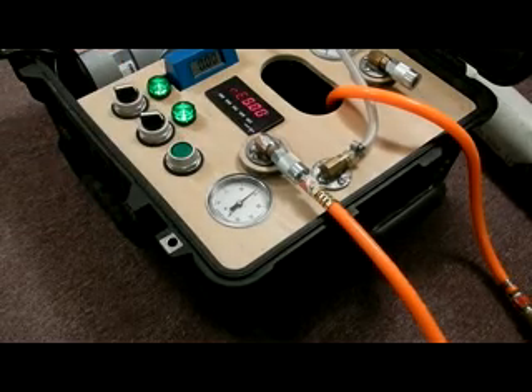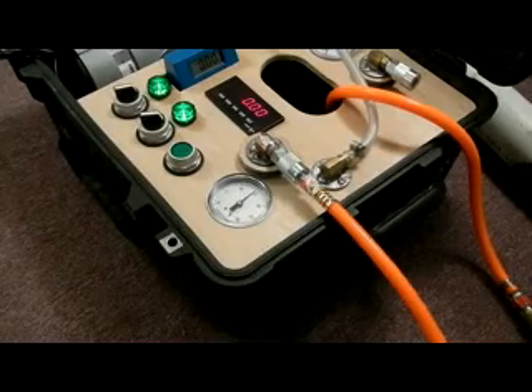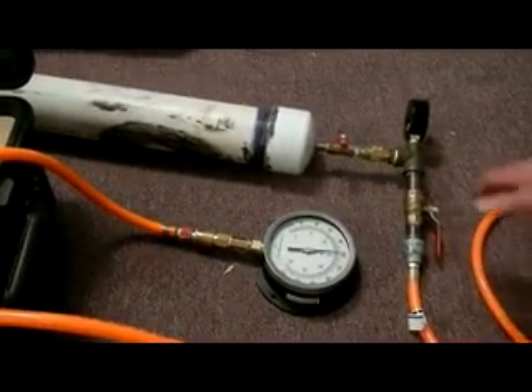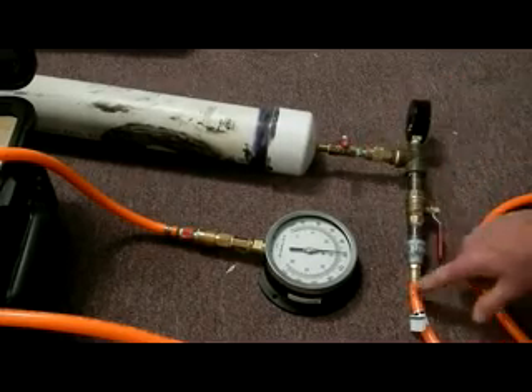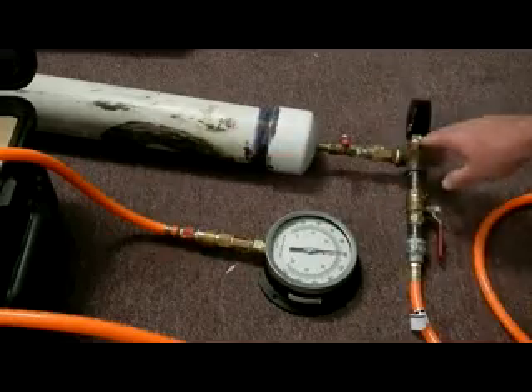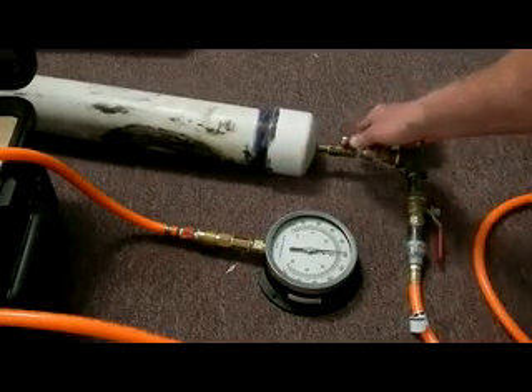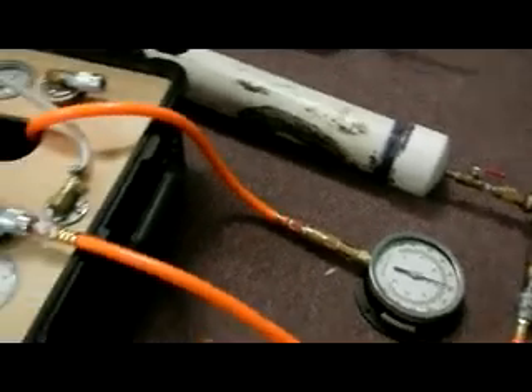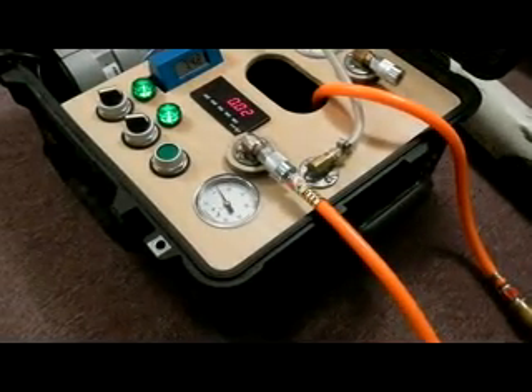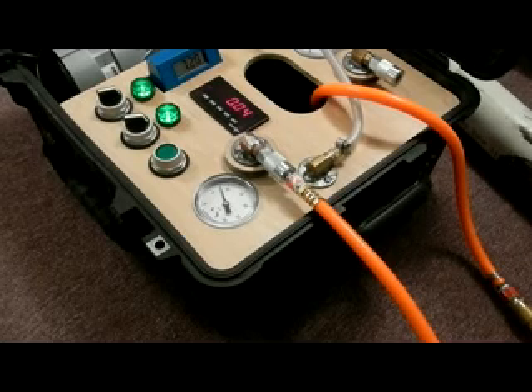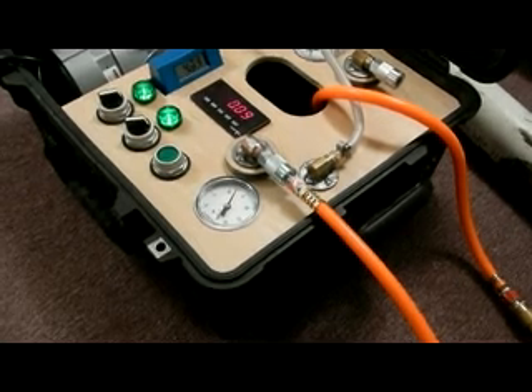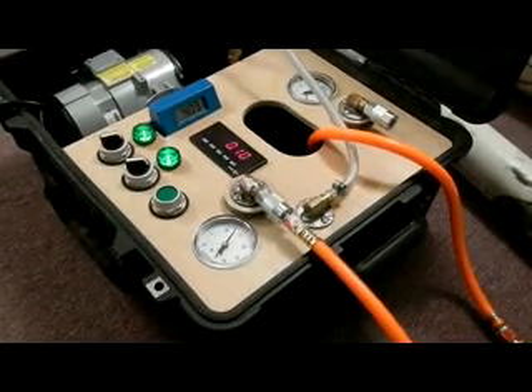We reset the counter because we don't want to count the hose. And now we're turning on. We're pressurized up to this point, and we reset to 0. We don't want to measure the hose. So as the pressure builds up, as the air is pressurizing the test cylinder or void, the flow rate in the blue meter is dropping down, yet the totalizer keeps counting up.